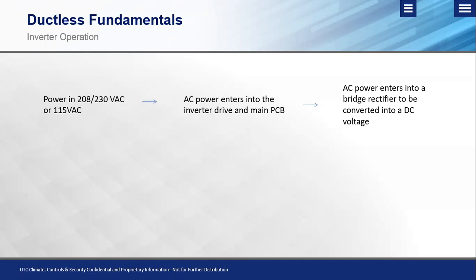Once we rectify the AC over into DC, we need to run that through what we call a reactor or an inductor. Whatever you're familiar with, technically both of them are right. I personally prefer inductor, but either one of them, as far as terminology is concerned, is correct. So essentially, the reactor or that inductor is a choke on the line itself. What it's doing is cleaning up the DC sine wave, or that newly generated DC power. Now, the reason that we do this is because we have an inverter-based operation. The name of the game, whether you're dealing with a ductless system or a larger commercial VRF system, is smooth, clean, consistent power. Okay, so that's why we're filtering not only on the DC side, but we also filter on the AC side to clean up the incoming power, and then more importantly, to clean up that newly generated DC voltage.